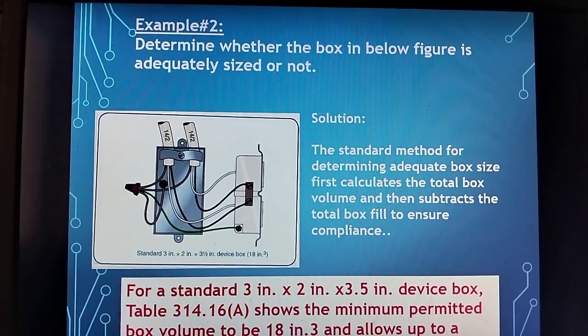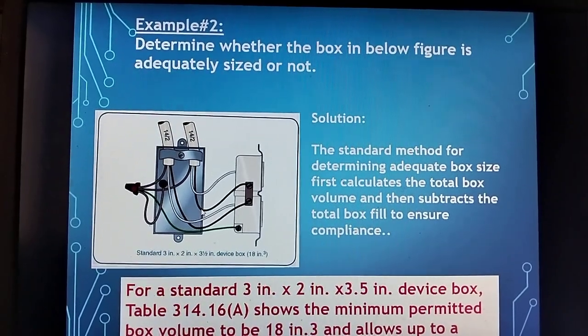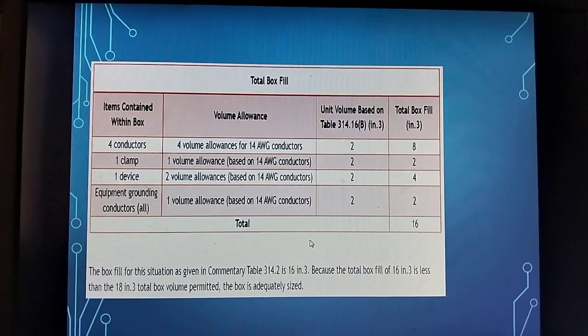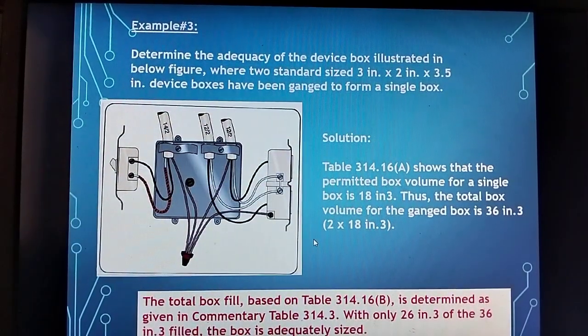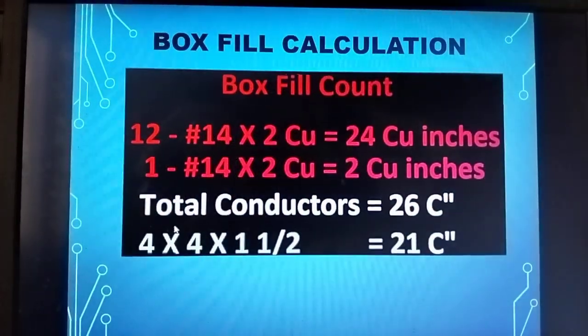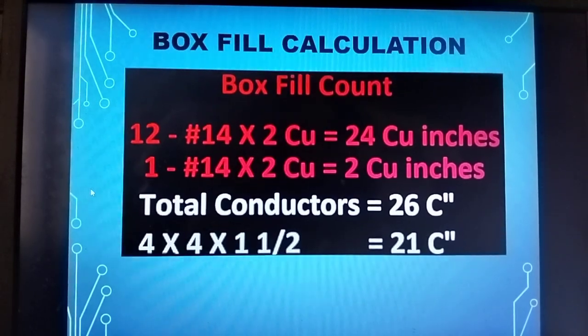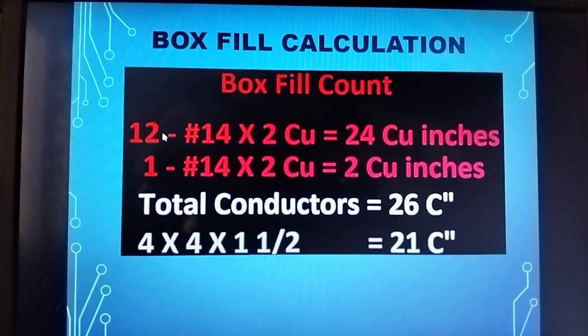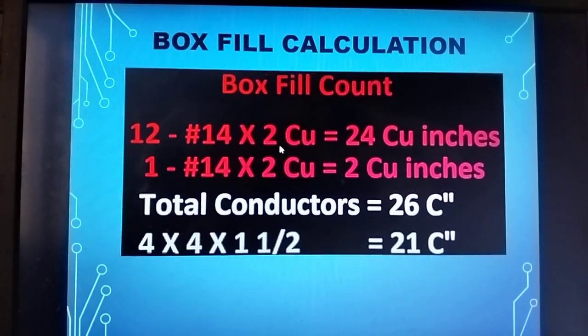Since the box has a maximum capacity of 14 wires, you follow the standard because you are using this size of utility box or device box. Here also you just calculate. This is the computation. Let's say you use 12 individual conductors, size 14. Size 14 has 2 cubic inches.